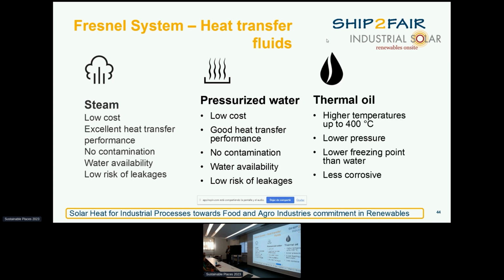And thermal oil is normally used only for systems with very high temperature. We call it the cut line above 230 degrees Celsius. The advantage of the thermal oil is the low pressure that you operate the system at, low compared to steam or pressurized water. The freezing risk is also normally mitigated. There are some oils that would freeze below -5, but in some cases they can go down to -20. It's less corrosive than steam, of course, but you also have the cost of the thermal oil. So for systems like that, it's important that they really need this temperature.